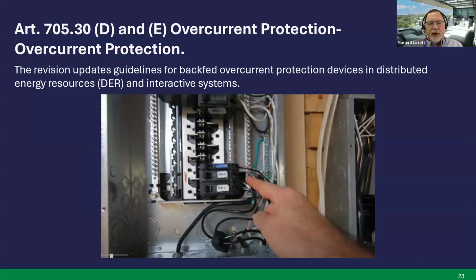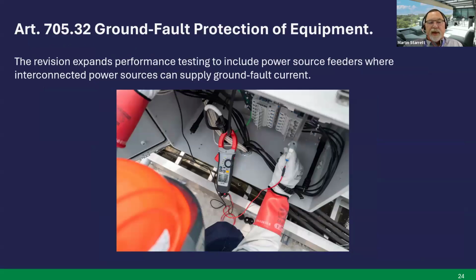Article 705.30D and E, overcurrent protection. The revision updates guidelines for backfed overcurrent protective devices in distributed energy resources and in interactive systems. It's more clarity and it's more listed out now. Next slide. Article 705.32, ground fault protection of equipment. The revision expands performance testing to include power source feeders where interconnected power sources can supply ground fault current. Next slide.